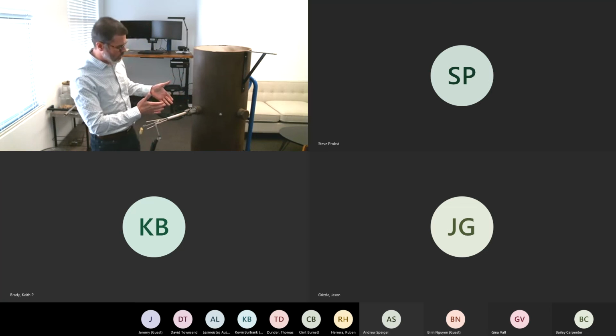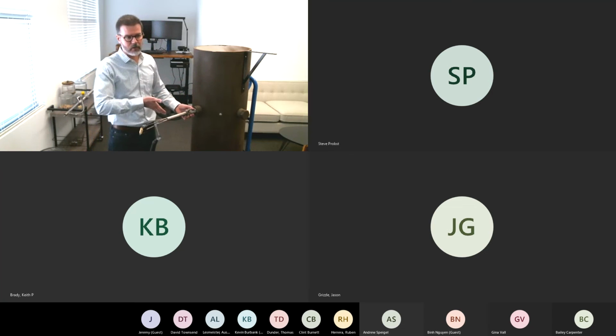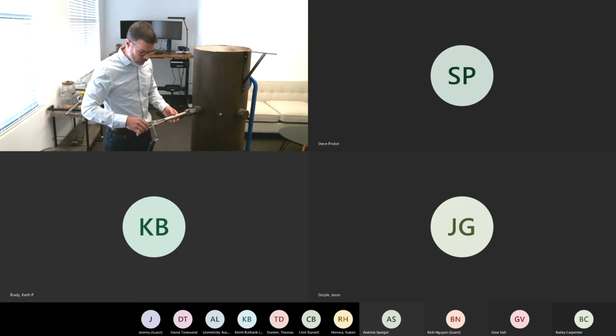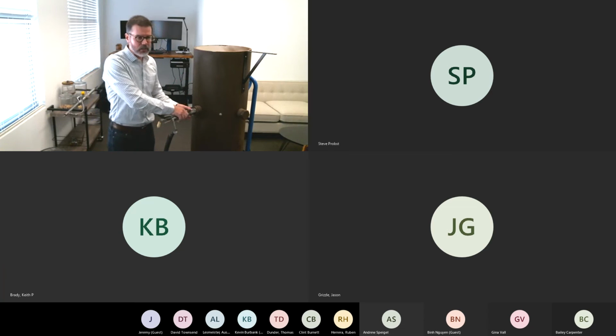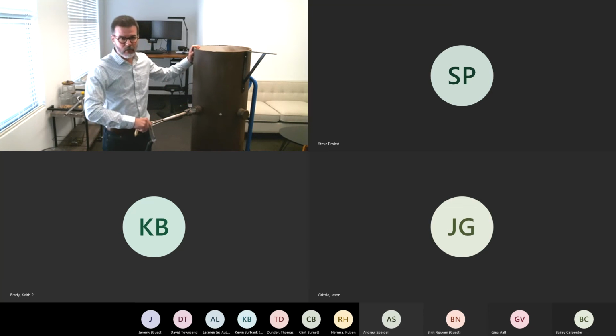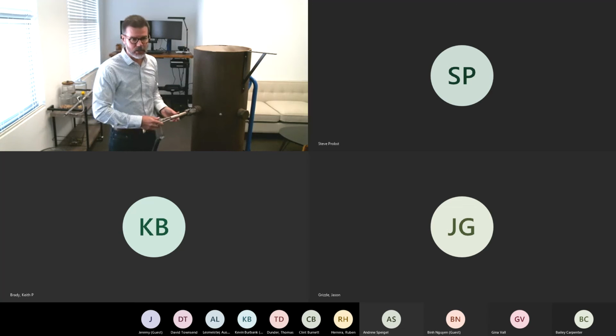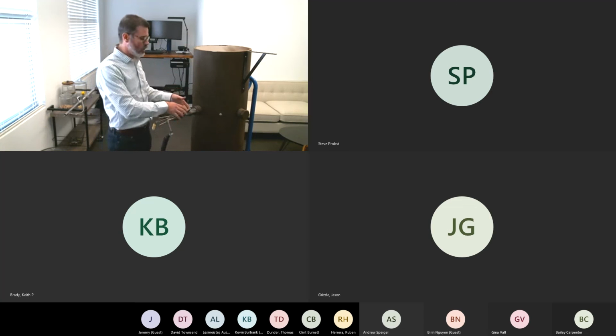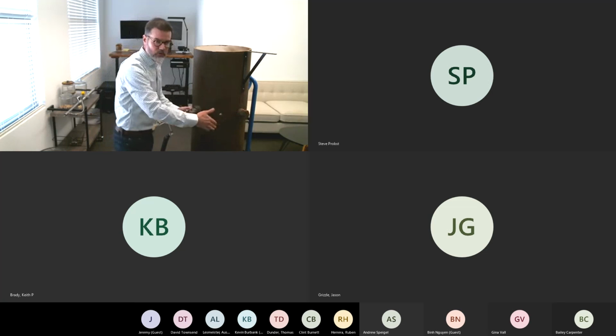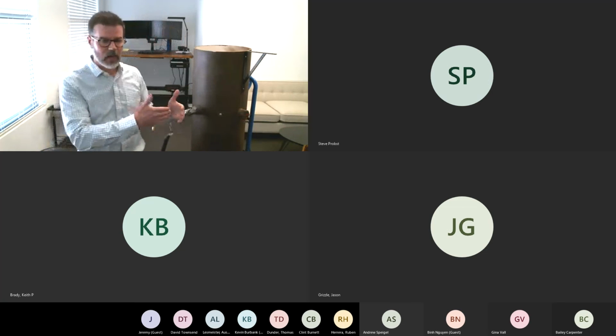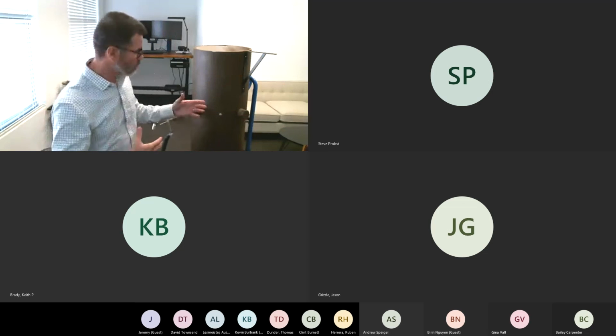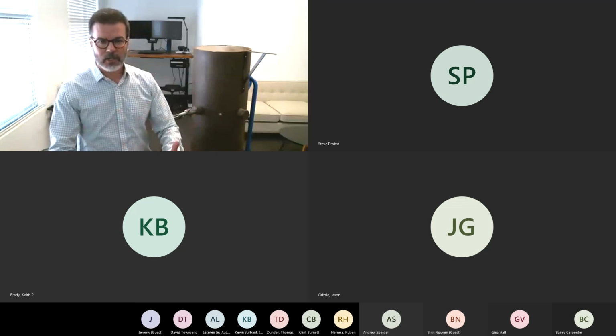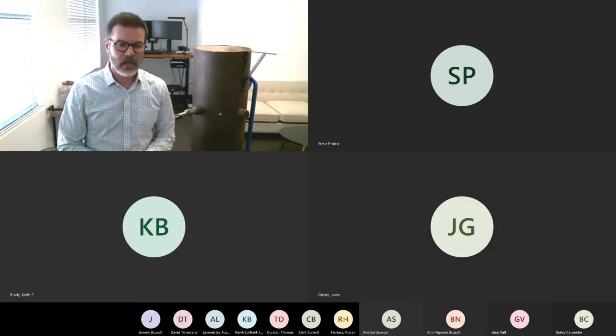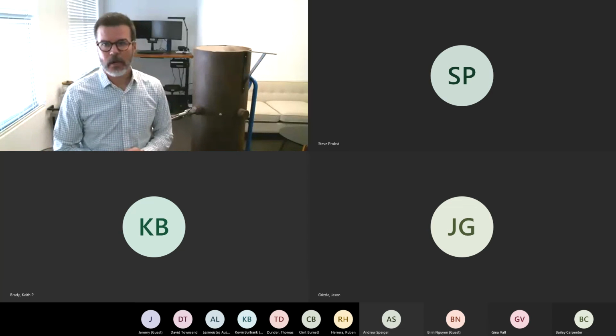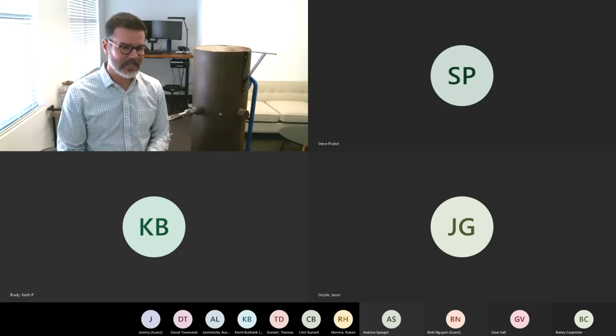So in order to do this properly, you mark your probe for the appropriate stack diameter. You go in. These can slide in. You can sample here across all of your points, your traverse points, getting your flow measurements. You can also sample here for concentration at your 3 points for your stratification check. And then once you're done here, you'll need to move the probe over and get into the other port, sorry, and get your measurements on the other line going through the center of the stack, and get all of your pitot readings to get your exhaust flow.